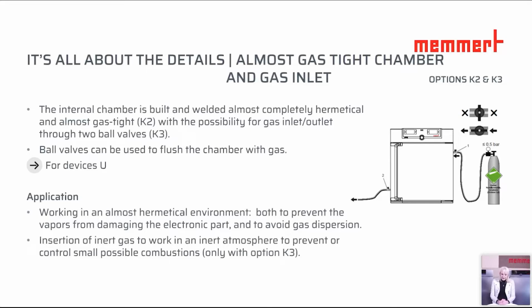We are now in the almost gas-tight chamber and gas inlet option, and this is widely used in electronics, for silicon rubber, semiconductors, in order to avoid chemical reactions, in order to avoid that the product is going to be destroyed. Mostly it's also used for the purge with nitrogen, which is also for cleaning purposes, for example. Here we have a chamber, and this is built and welded almost completely hermetical and almost gas tight. This means this is nearly gas tight and will not have the opening, which is normally in the bottom, to put in fresh air, and it also will not have a flap at the rear. So it's almost tight. And then we have this possibility for gas inlet and outlet through two ball valves.